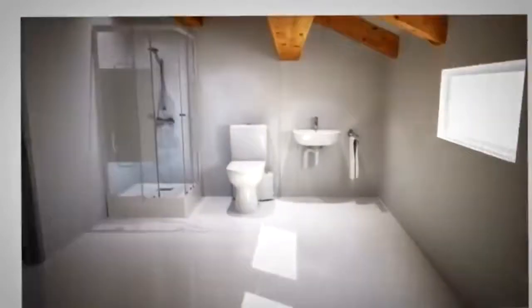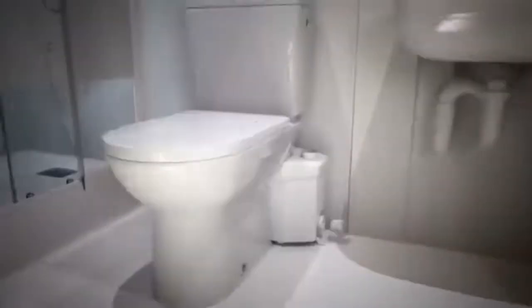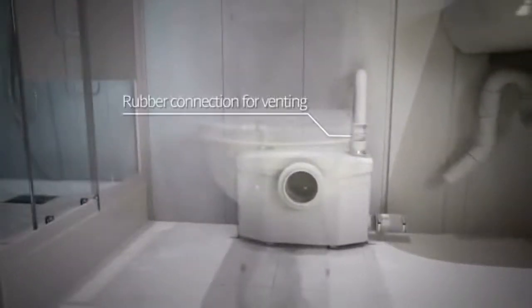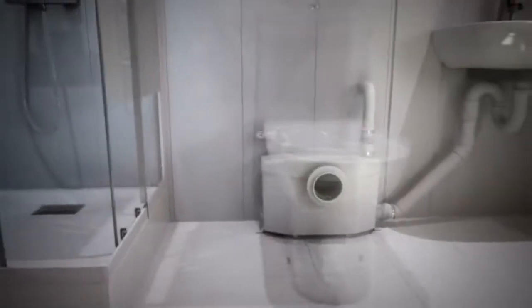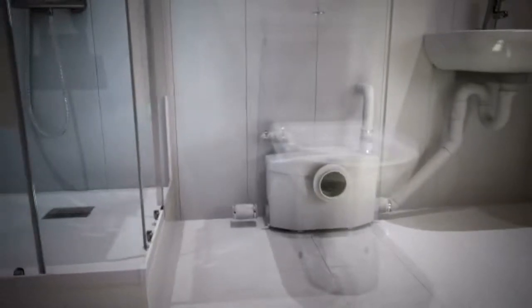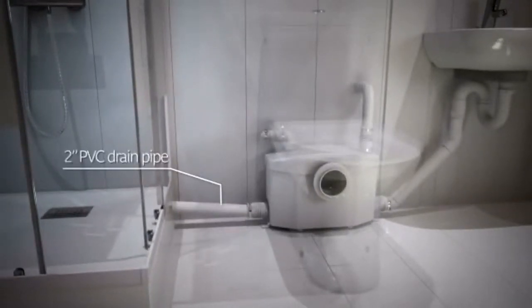The concept is simple. Our macerators are easy to install. Install a vent connection on the macerator using the coupling provided in the installation kit. Connect the drain pipe from the sink to the lower 2-inch inlet on one side of the macerator. Connect the drain pipe from the shower to the opposite side inlet.